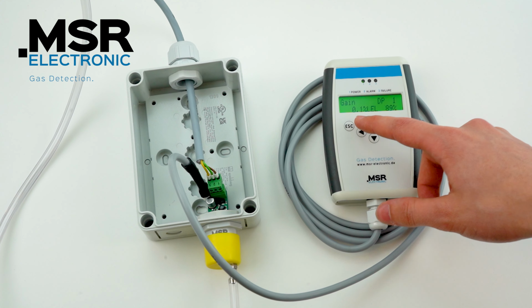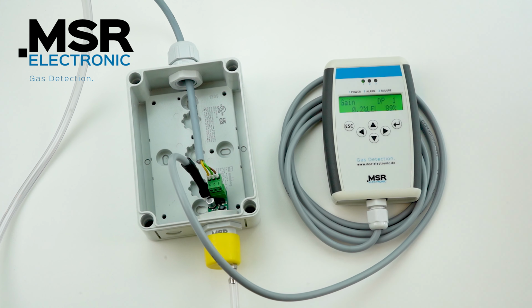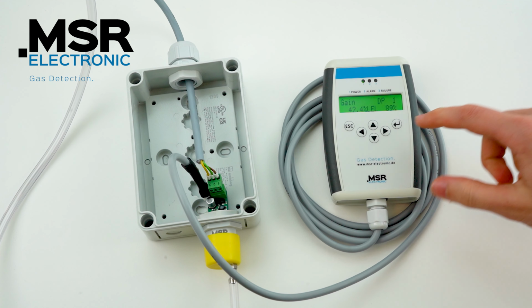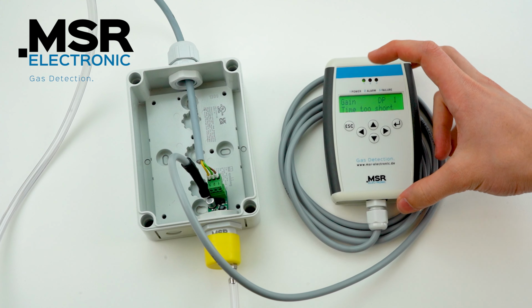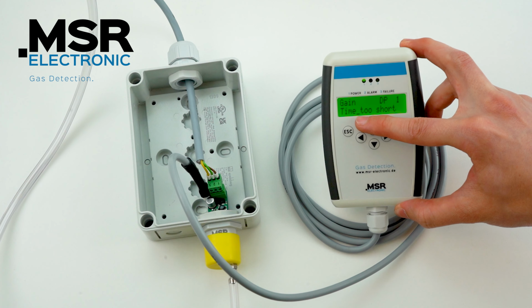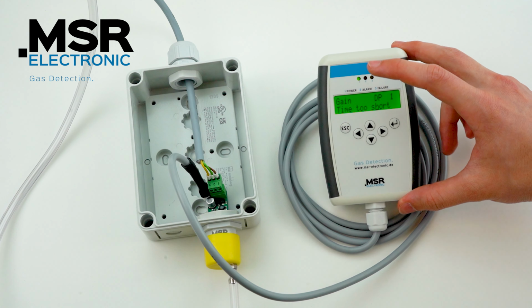The gas application time for the sensor can be found in the user manual for the sensor. In my case, this is 2 minutes. After the specified time has elapsed, the new value can be saved with the enter button. Important here, be sure to wait for the full gas application time before saving the value. Do not save too early.